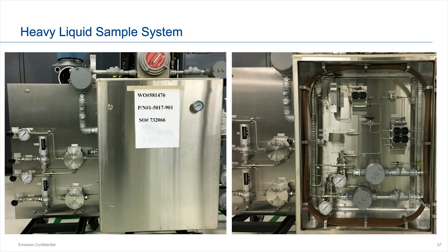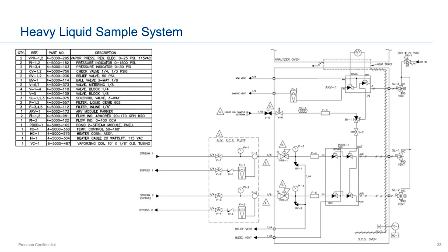The heavy liquid system also has a double block and bleed for two-stream switching, an ARV, flow control, a vaporizing coil for liquid calibration gas, and additional filtering after the vaporizer. Heat tracing runs throughout to maintain temperature. The schematic shows the full sample conditioning plate layout including solenoid switching between the two streams, the vaporizer coil for liquid calibration, and the vaporizer for the liquid sample itself.